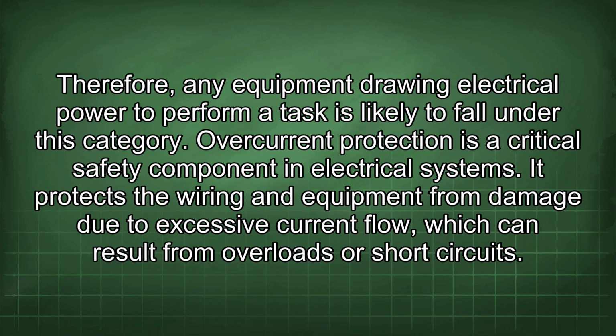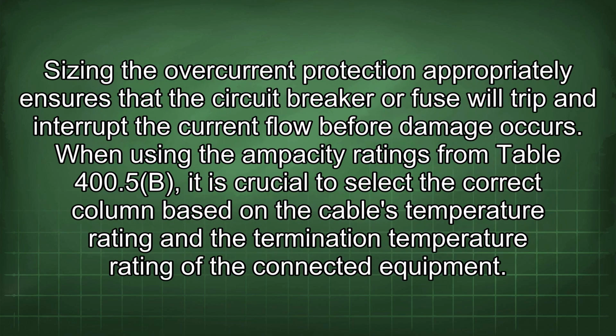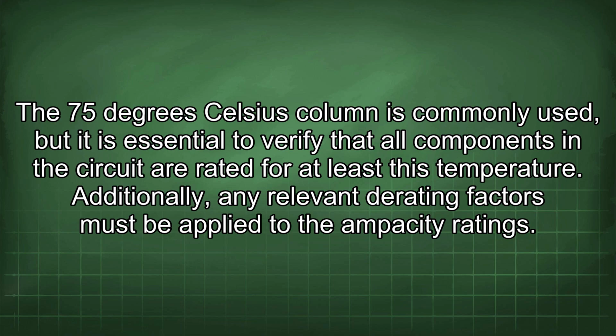Overcurrent protection is a critical safety component in electrical systems. It protects the wiring and equipment from damage due to excessive current flow, which can result from overloads or short circuits. Sizing the overcurrent protection appropriately ensures that the circuit breaker or fuse will trip and interrupt the current flow before damage occurs. When using the ampacity ratings from Table 400.5b, it is crucial to select the correct column based on the cable's temperature rating and the termination temperature rating of the connected equipment. The 75 degrees Celsius column is commonly used, but it is essential to verify that all components in the circuit are rated for at least this temperature.